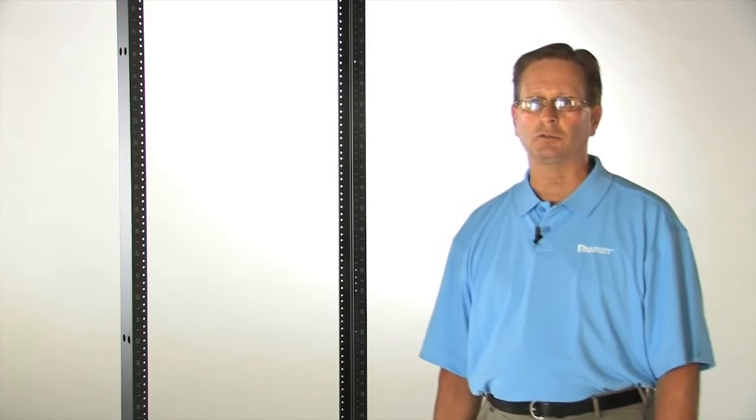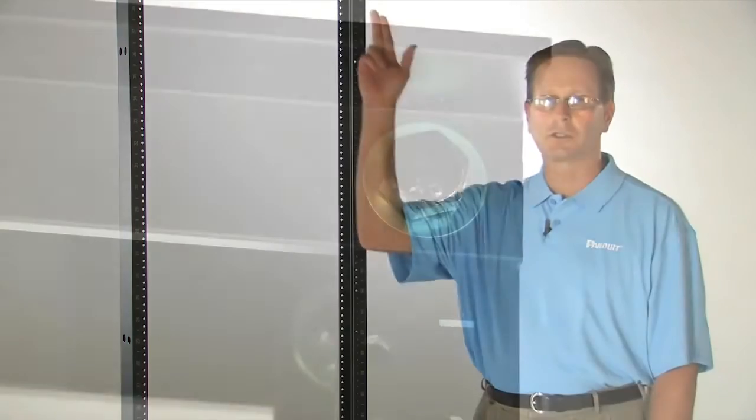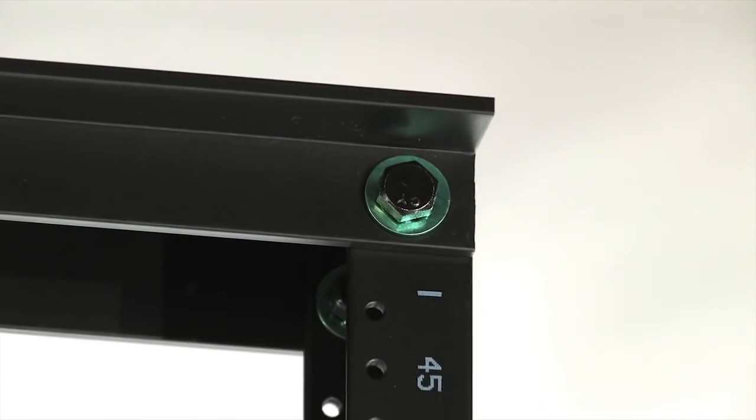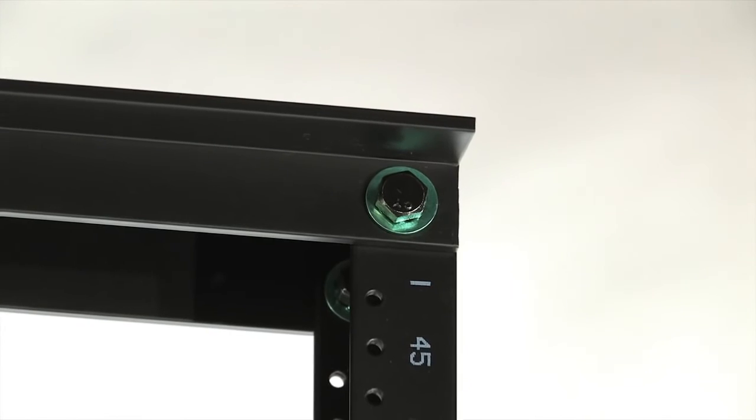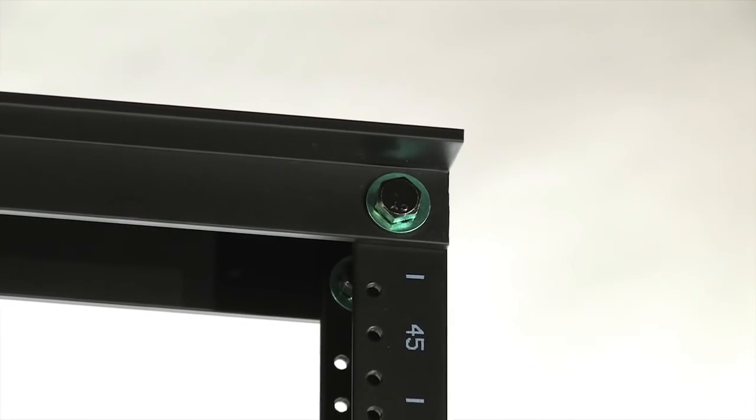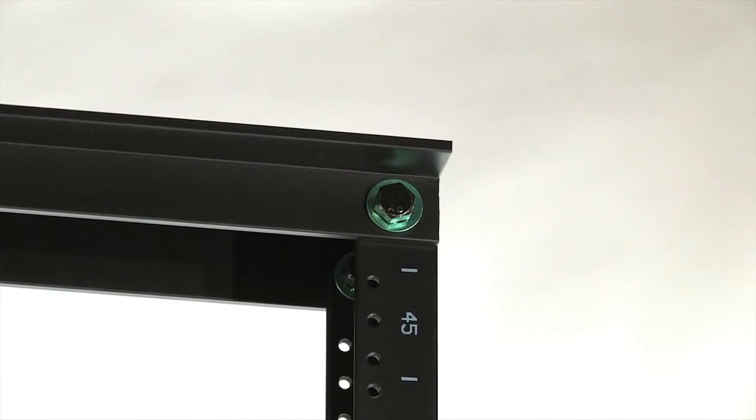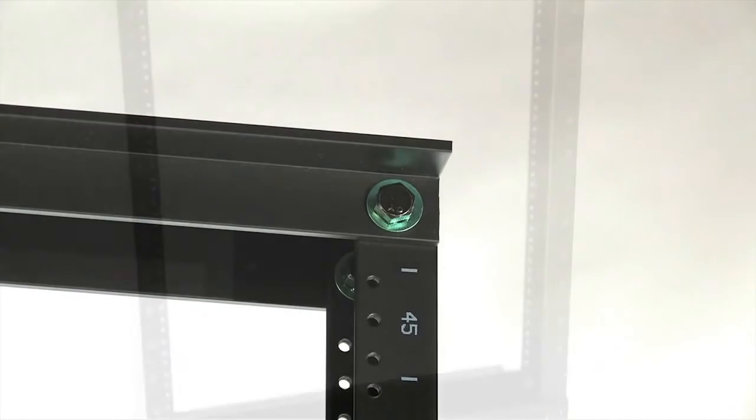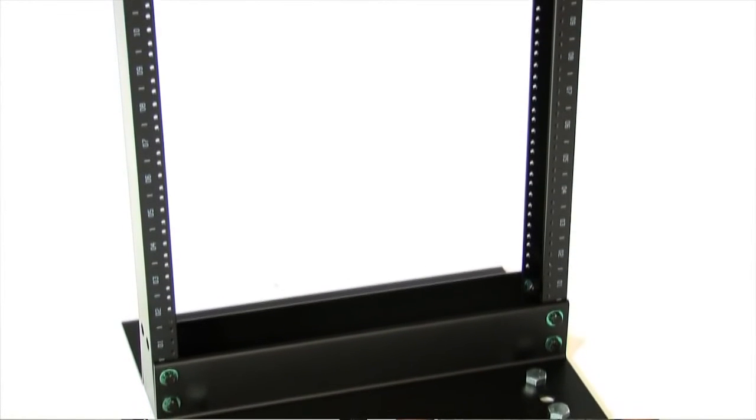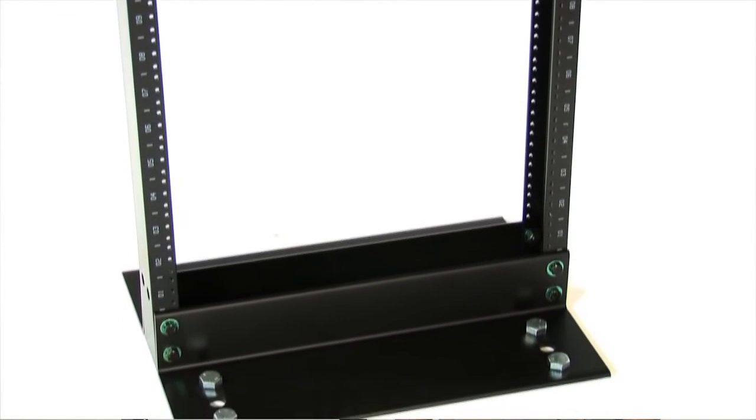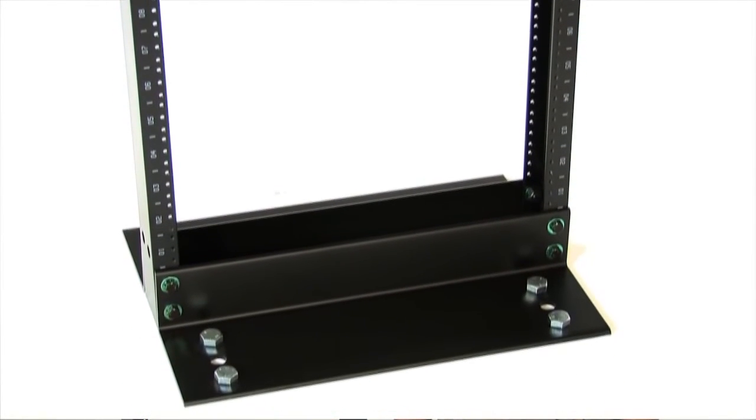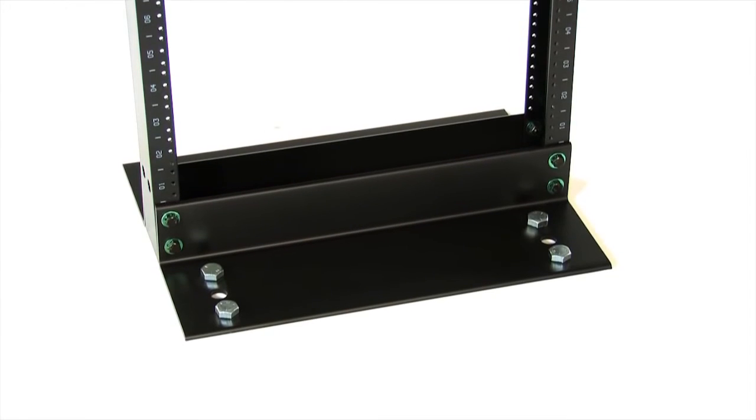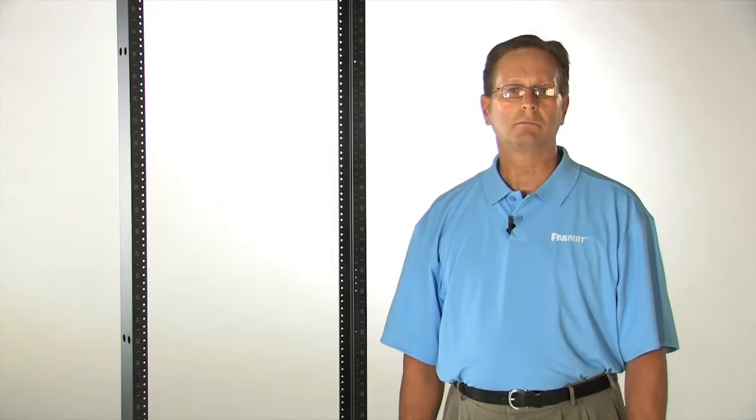Unique features of the Panduit two-post rack include a fully-bonded structure such that all the metal parts used on the rack will be maintained at ground potential when connected to a grounding system. This effective grounding minimizes noise coupling to the data equipment. Grounding also assures that defective equipment will not be able to charge an ungrounded piece of metal.